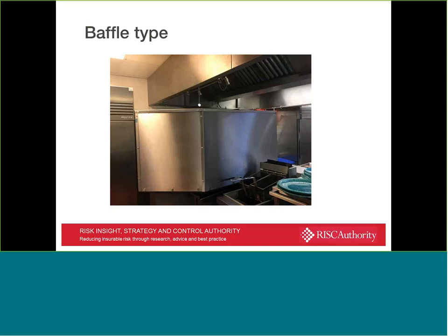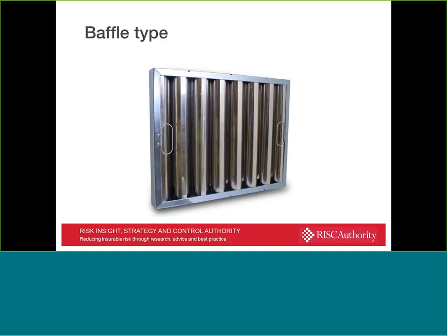We can also have baffle type filters, and apologies, I'm not sure the photo is particularly clear, but baffle type filters have a series of interlocking vanes in them, which creates changes in direction of the airflow, which traps the grease, and the grease then is released to run down into a collection tray or a collection drawer where it can be cleaned from. And because of the way the grease is almost extracted from the airflow and isn't held within a mesh and can be taken away, it reduces the potential for ignition at that particular point. That's just a clean, shiny one up close.